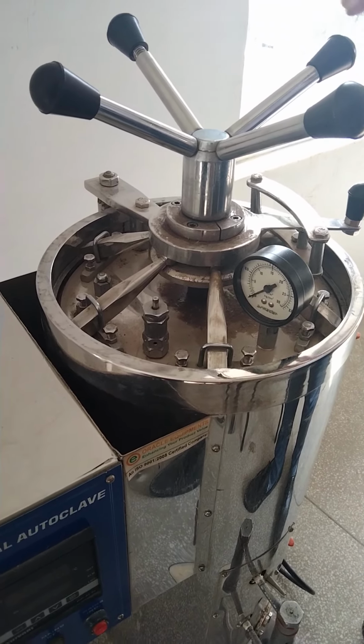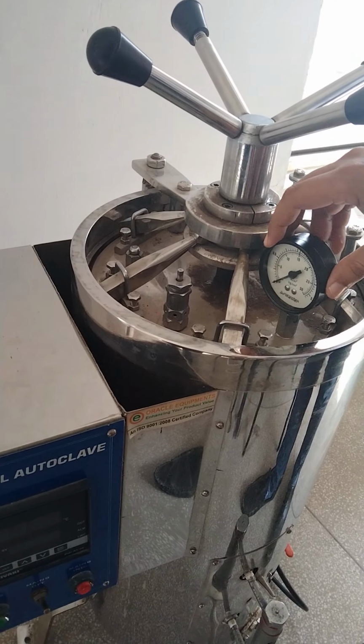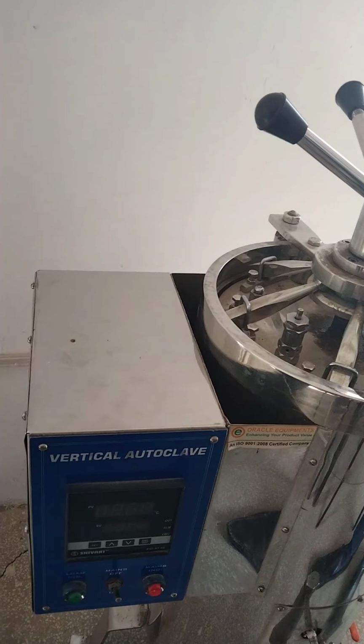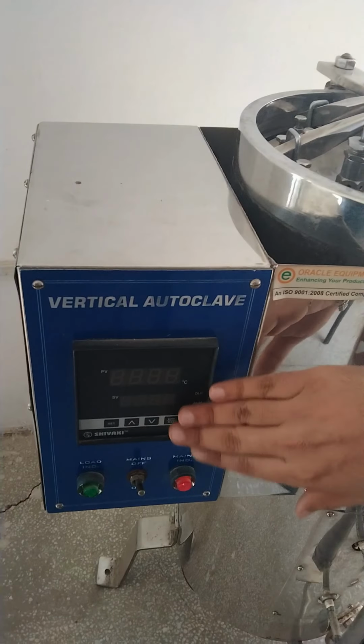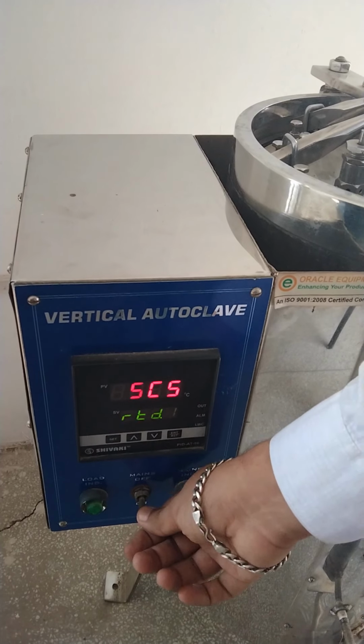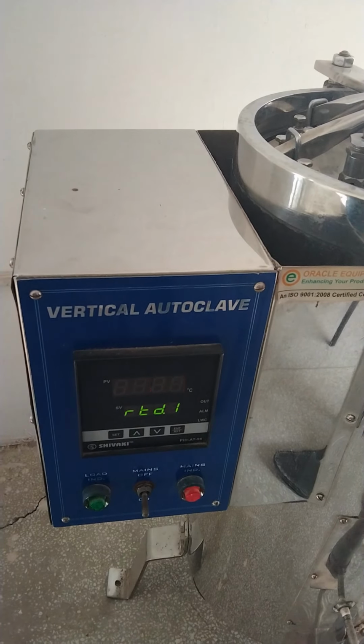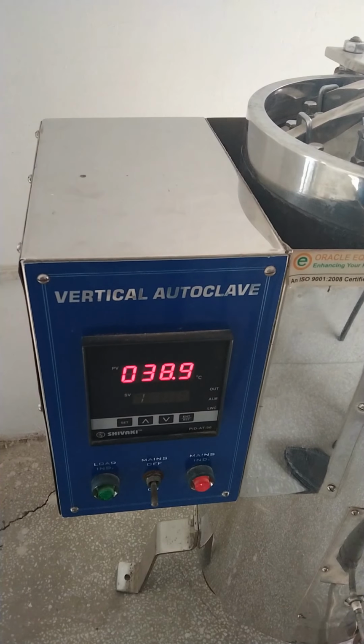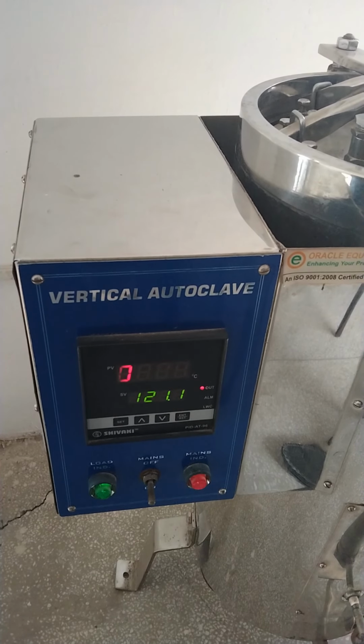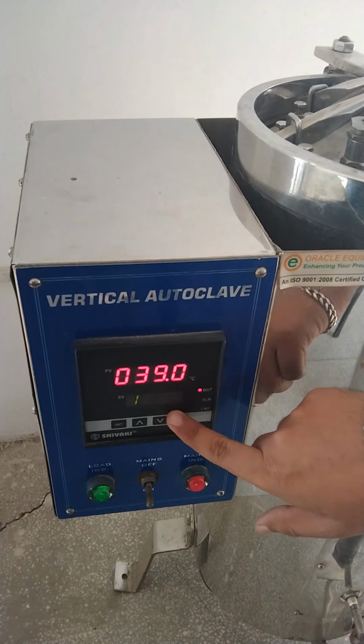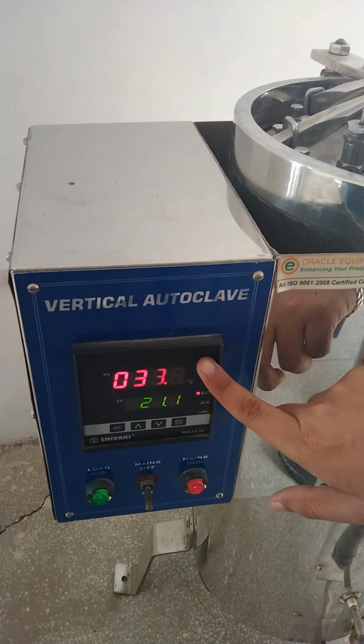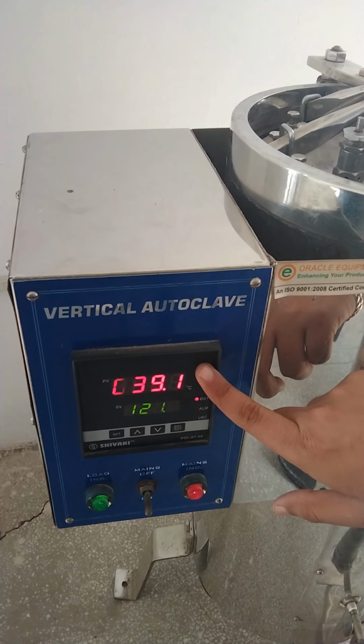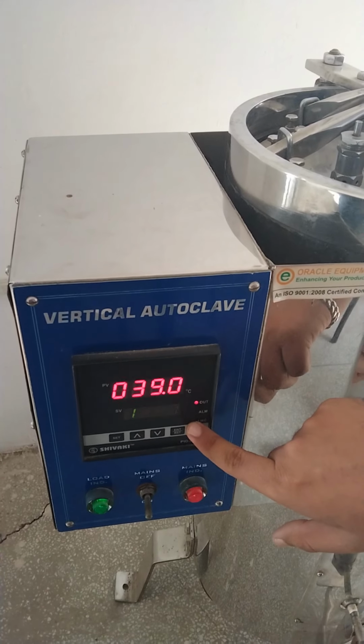As you can see over here, the next component is the temperature controlling devices. Thermostats are already present, and this is the display unit. As you switch on the main switch, you can see here the set value, and the value above indicates the present value. As you can see, the set value is 121.